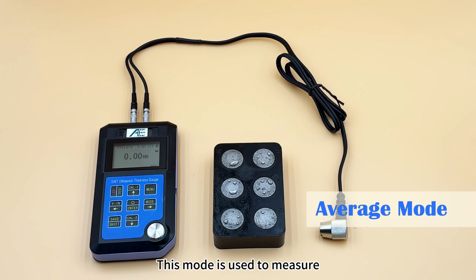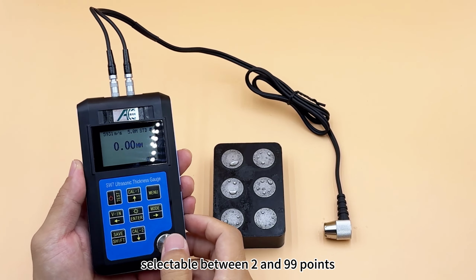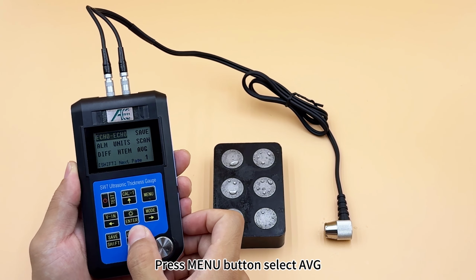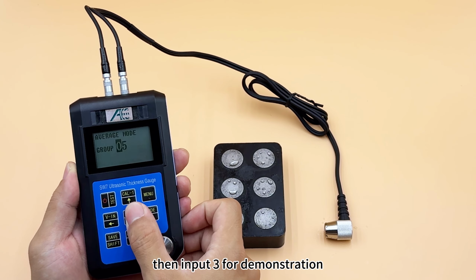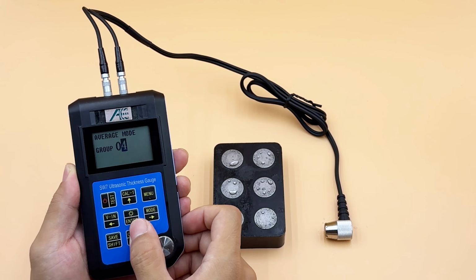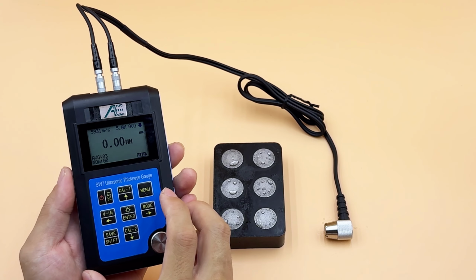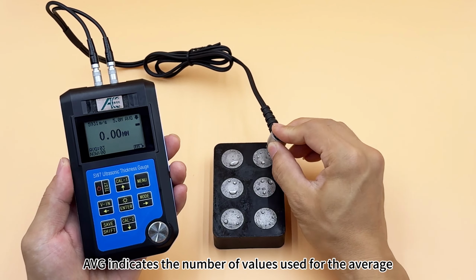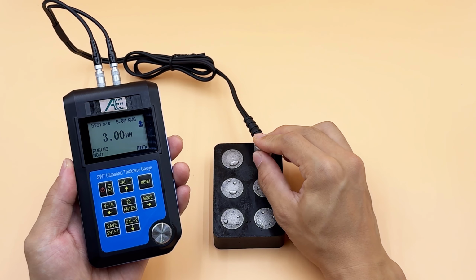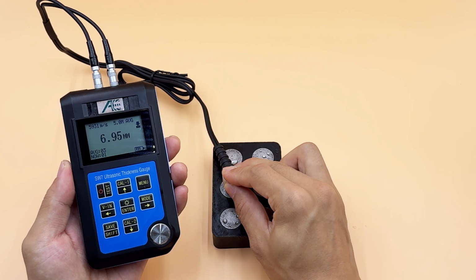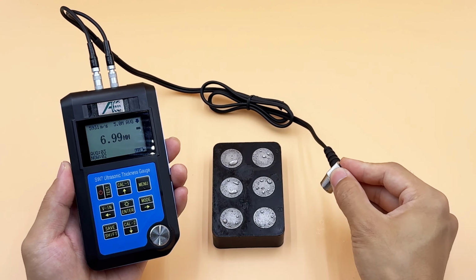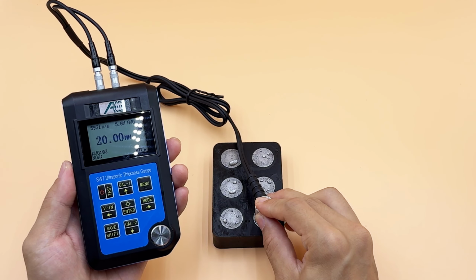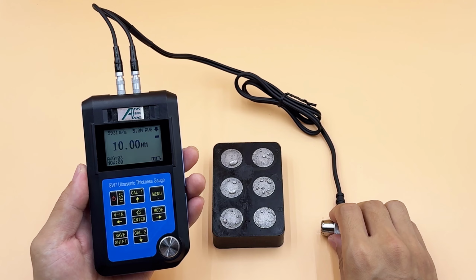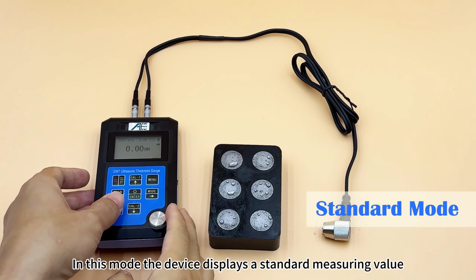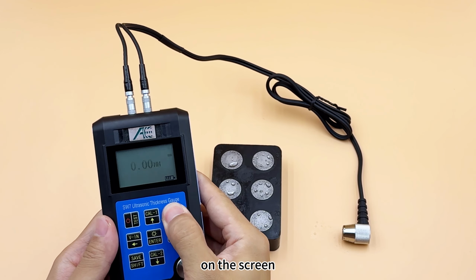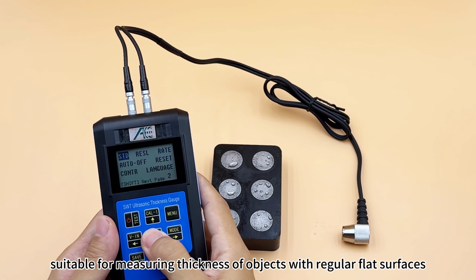Average mode. This mode is used to measure the average value of multiple measurement points, selectable between 2 and 99 points. Press Menu button, select AVG, then input 3 for demonstration. In the measuring interface, AVG indicates the number of values used for the average, and now shows the current measuring point. Standard mode. In this mode, the device displays a standard measuring value on the screen, suitable for measuring the thickness of objects with regular flat surfaces.